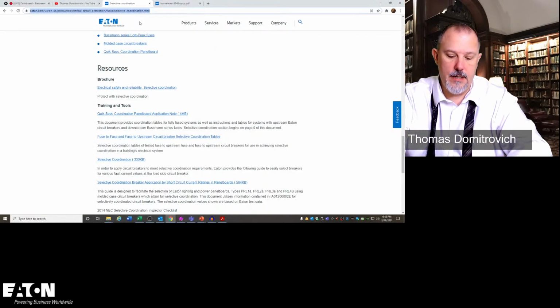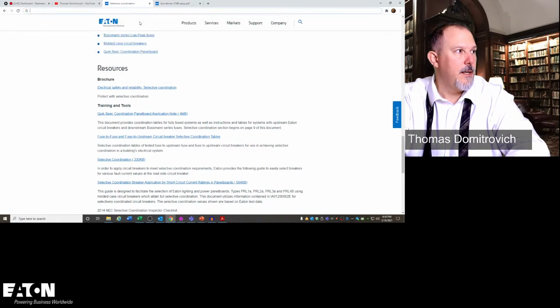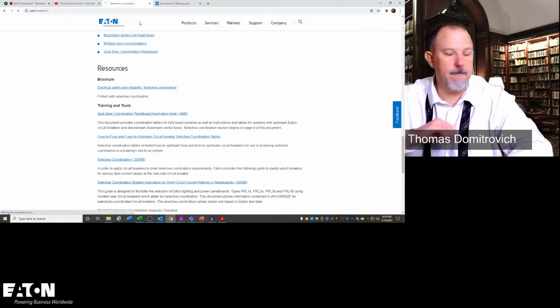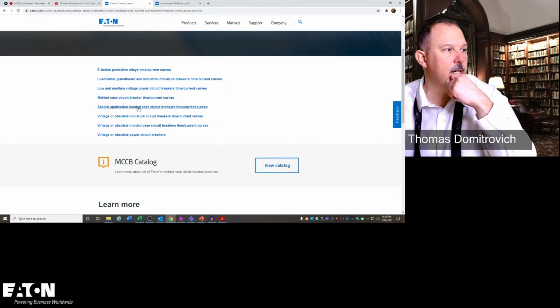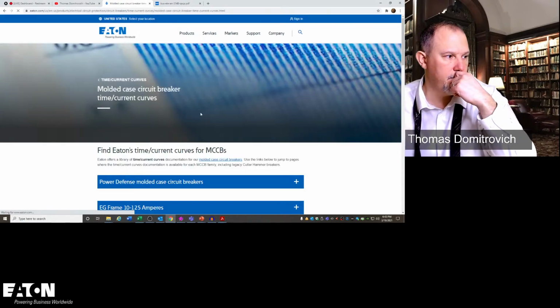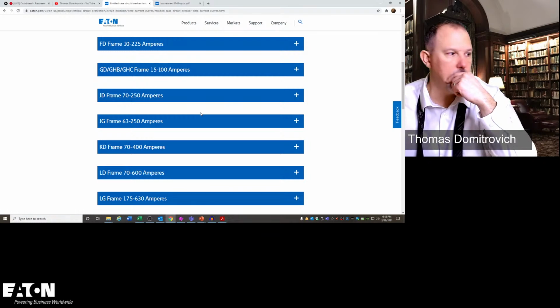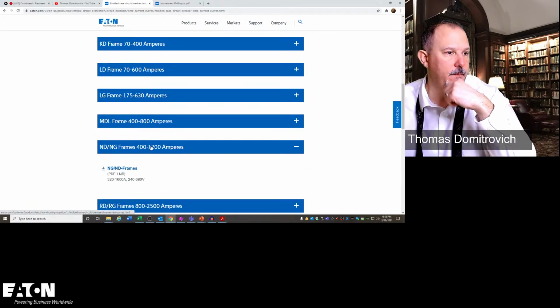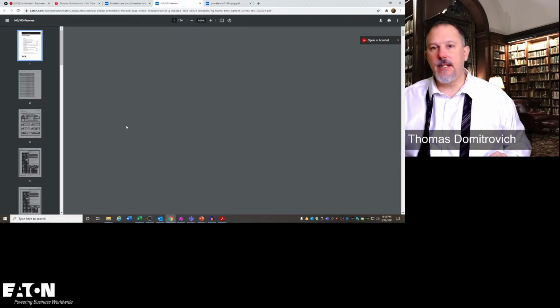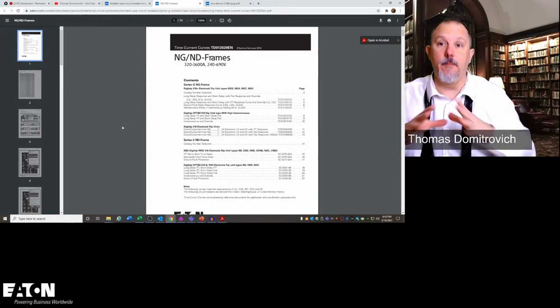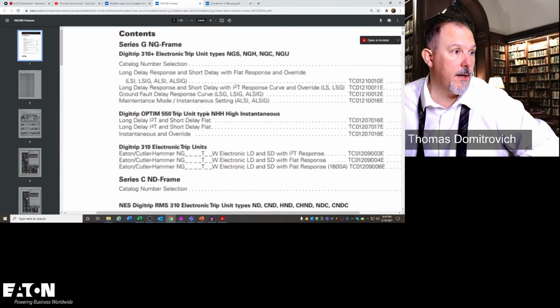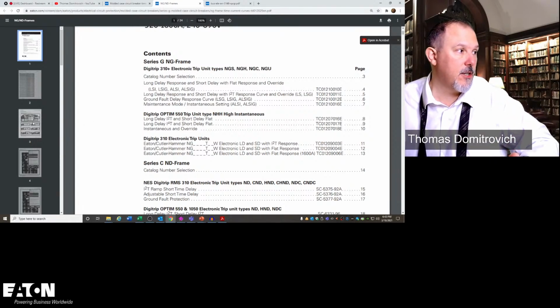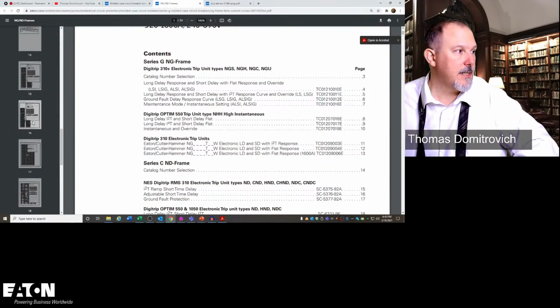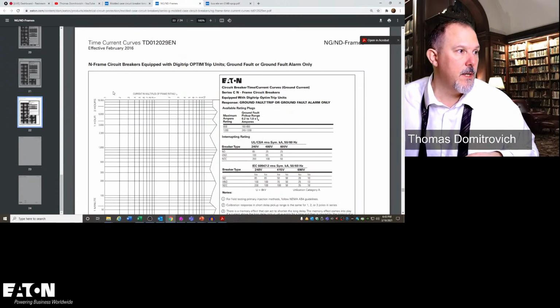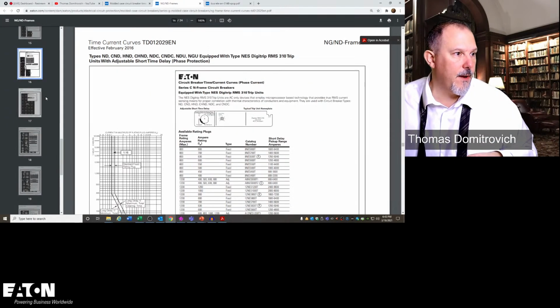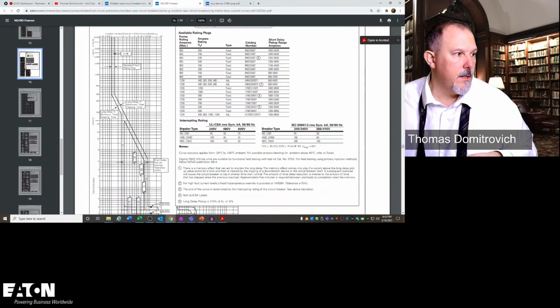Let's go to Eaton.com/TCC. And I'm going to go to molded case circuit breakers, and I'm going to go to the N frame. I'm going to look at the ND breakers. All right. So I'm really getting deep in the hoopla here, because now I'm going to the actual TCC curve, and I'm not using SKM at this point. I've popped out of SKM. So I need an 800 amp frame breaker. There's my 800 amp frame.